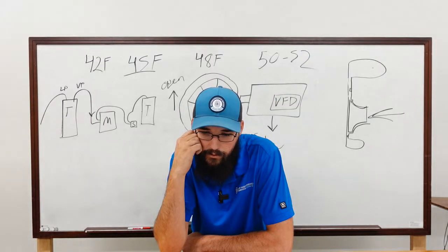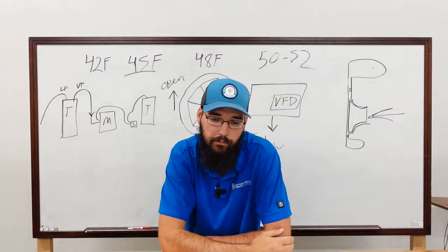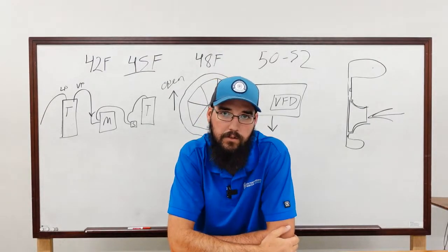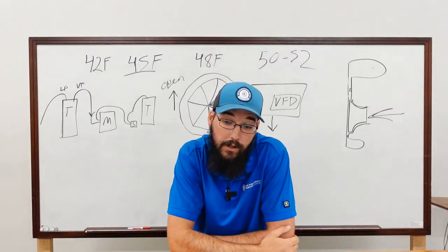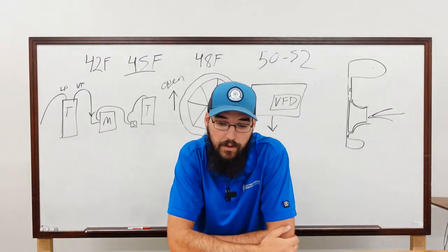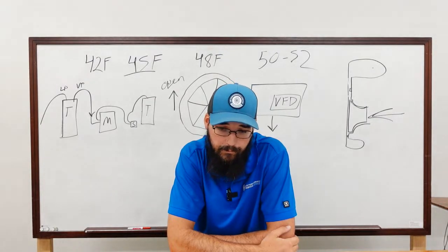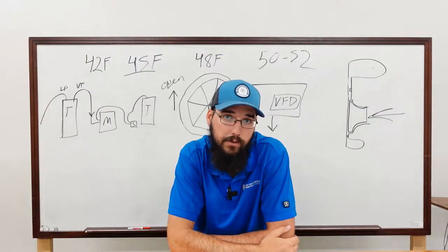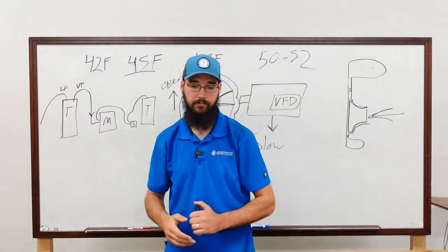Ever recover liquid while running the compressor? Yes, on small systems. We'll use compressor assisted recovery is the term I use for it, at least. Anyway, it is something we do on a smaller system. It is not something I would personally want to do on, say, a centrifugal. I personally wouldn't practice that. But y'all got y'all's own thing figured out over there, so not going to say you shouldn't do it.